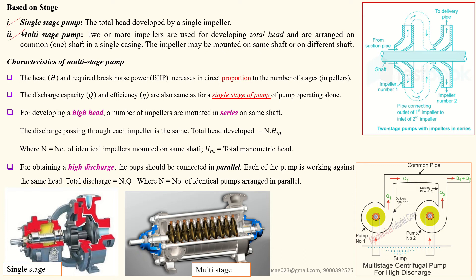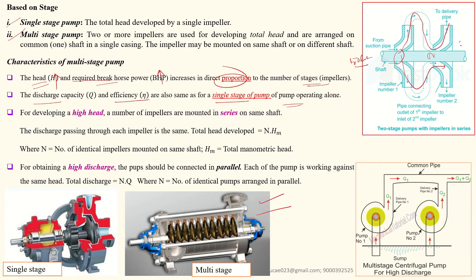The main characteristics of multi-stage pumps: head and brake horsepower increase directly proportional to the number of stages — as the number of stages increases, the head and power consumption also increase. However, discharge and efficiency remain equal to a single-stage pump operating alone. For example, if the first impeller draws 50 liters, the next impeller does not draw additional water — it only sends the same 50 liters forward. So the total output discharge remains 50 liters.